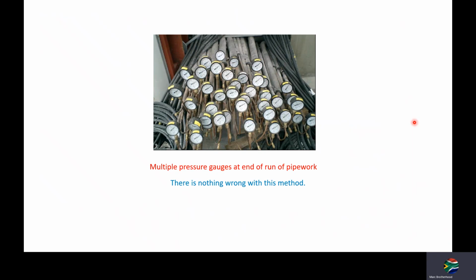Also very, very important, when you do pressure testing, take a recording of the outside ambient air temperature. Let's say it's 30 degrees outside, just make a note that it's 30 degrees, and if you're pressure testing to say 30 bar, you might come in the morning and the pressure's dropped. You want to check on your pressure. You will notice that the pressure gauges have all dropped a bit, and you'll think there's a leak on the system. There's no real leak on the system, it's just the outside air has dropped, and it's also caused the pressure to drop in the pipework.